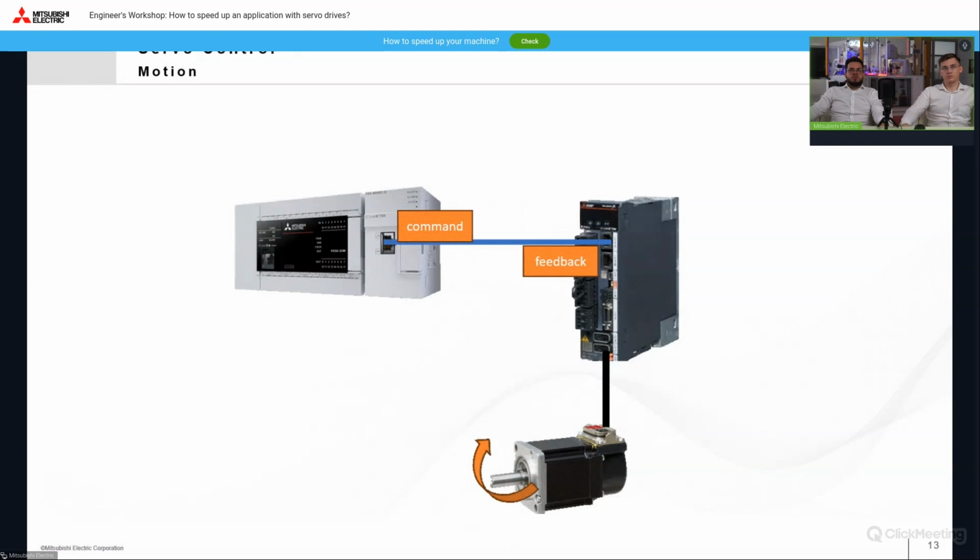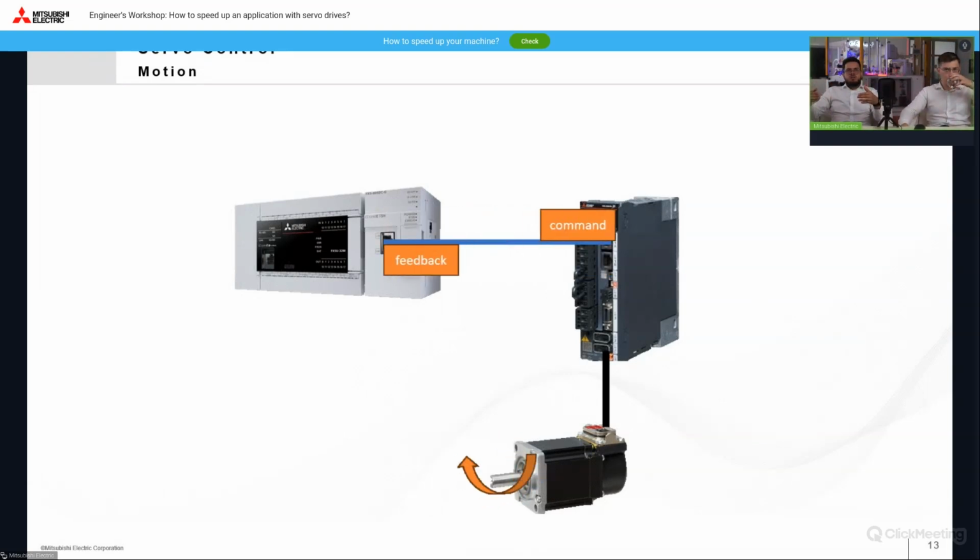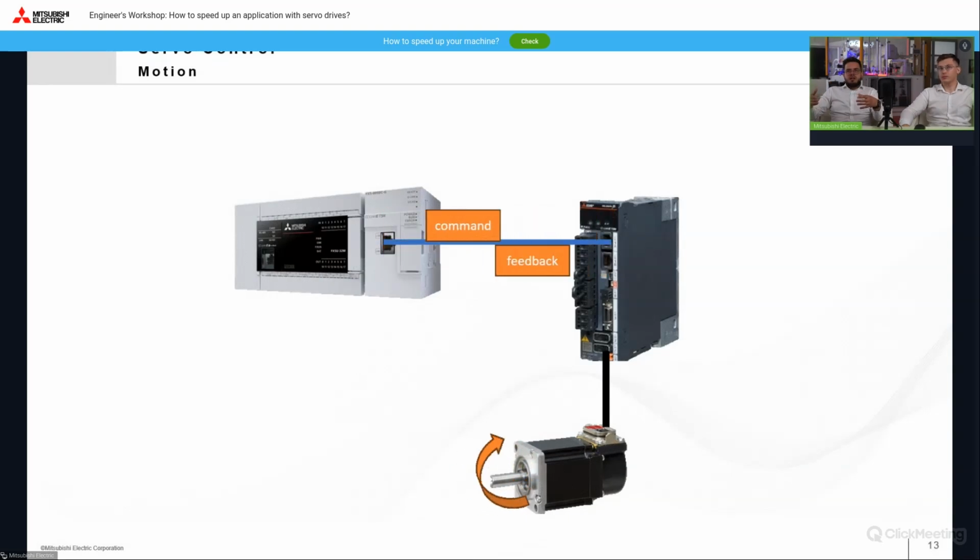Second, motion control, on the other hand, is where the motion controller monitors position loops and sends each drive a new target. So you can work multiple drives in collision space and pass each other without wasting time until one or the other drive moves away. This is possible because it's the motion controller that calculates the trajectory of the drive's movements, and we can build more complex paths without overloading the amplifier.